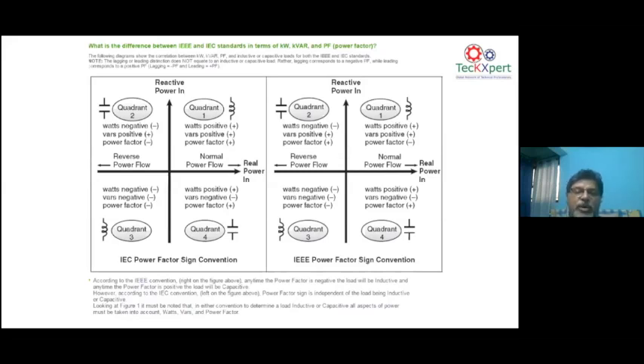The 4-quadrant operation is basically this: a power factor controller or any other active filter that you're using for correcting leading power factor, if it can do 4-quadrant operation, the advantage is that whenever you are in quadrant 1, you are consuming power from the grid. I'm assuming myself as a user, for example, consuming power from TNEB. When I'm in quadrant 1, I am drawing reactive power as well as real power from the grid.